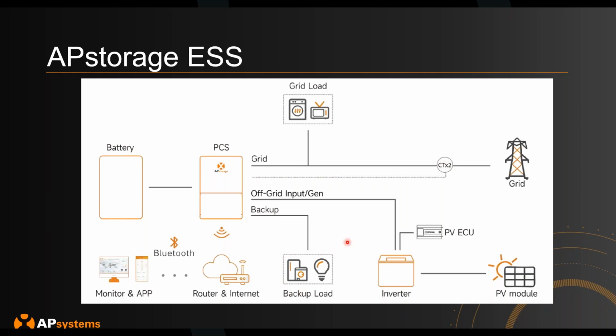A question people often ask is whether solar can stay on during a grid outage. You connect your inverter system in here. People also ask which inverters you can use—can you use DS3s, our older microinverters, or another brand's microinverters? The quick answer is yes, because if you AC couple solar into this port, it will turn on 240V when it wants solar during a grid outage, and turn it off when the batteries are full to prevent overcharging. Any inverter that delivers power to AC will not produce power if it doesn't see AC voltage on this port, so basically any inverter solution can go into here.